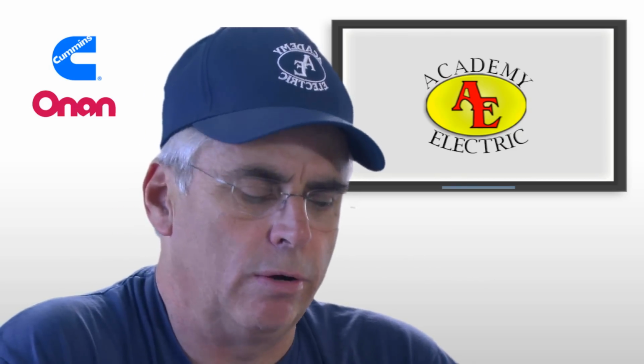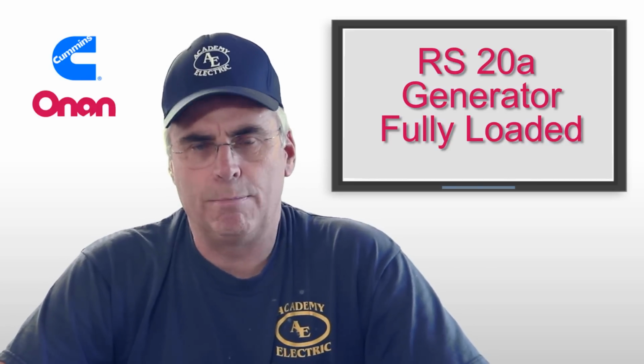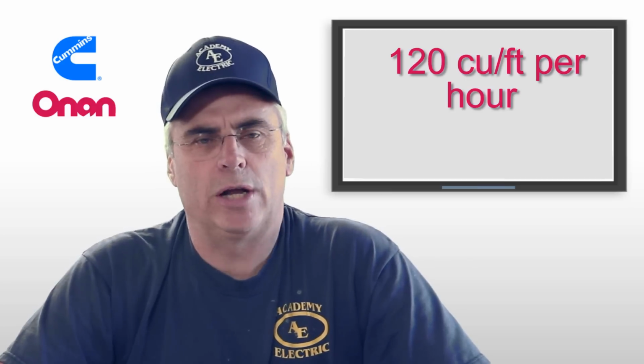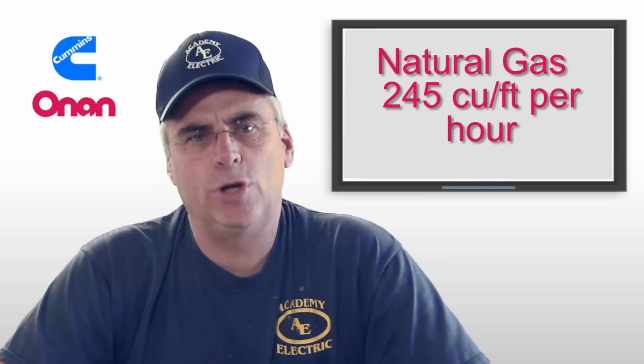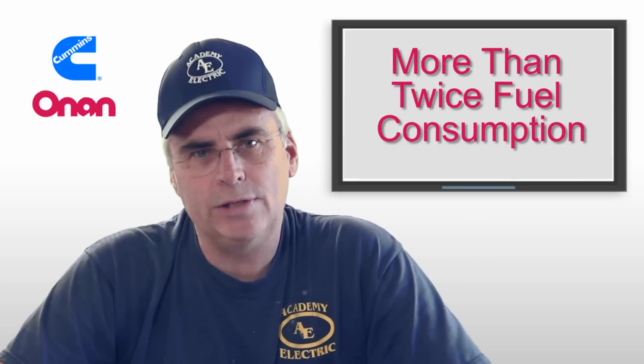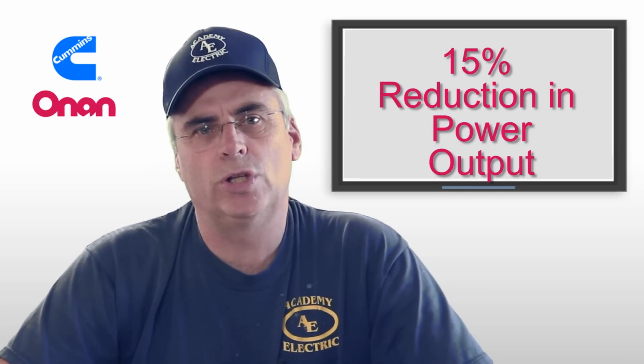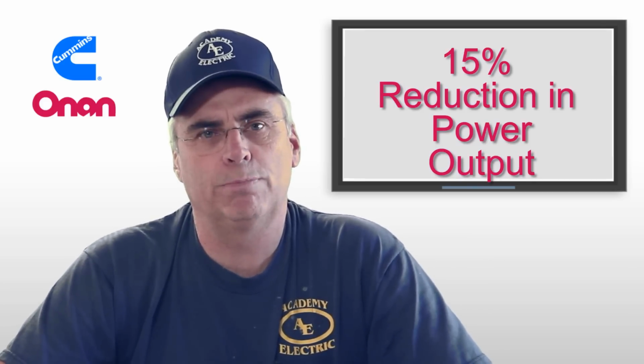Talking about fuel an hour, an RS-20A generator fully loaded on propane consumes 122 cubic feet of gas an hour. That same generator, fueled on natural gas, is 245 cubic feet of gas an hour. So it's almost better than twice the amount of fuel in cubic feet an hour on natural gas as it is on propane. And there's a 15% reduction in the power output of the generator on natural gas versus propane.